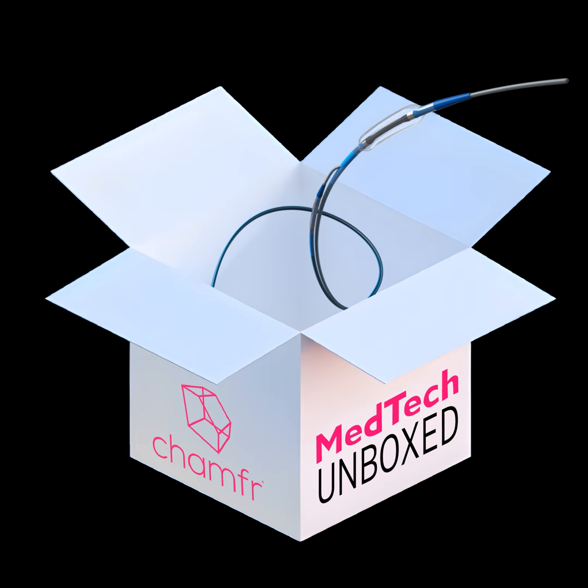So then we went in and tried a couple of other approaches. Standard PEBAX, but it was too tacky. We tried Vestamid ML21. It was too hard, but still not lubricious enough. So we ended up integrating the EverGlide Plus 60 durometer, the high durometer version of the EverGlide Plus, into the structure. And yes, we do have damage when the implant is a sharp object going through the ID when we use the EverGlide Plus, but the failure mode is slightly different. It's more like a cutting board creating a dent versus a banana, like a PTA, which would just peel. So we see a little bit different failure mode. In that application, it has proven to be a better choice because of the failure mode of the material.